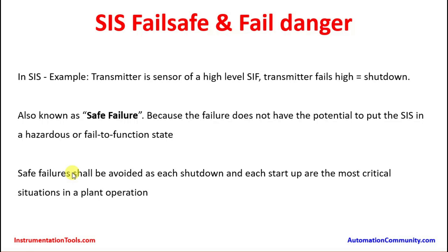Safe failures shall be avoided, as each shutdown and each startup are the most critical situations in plant operation. Plant startup and shutdown require significant manpower and many maneuvers to bring the plant from zero state to normal operating condition, or from full production to shutdown — which can take half a day, one day, or two days depending on plant capacity. The plant uptime and downtime is most critical.